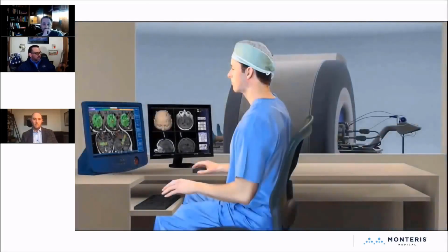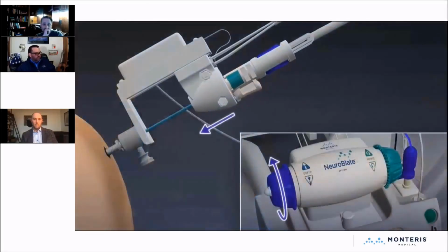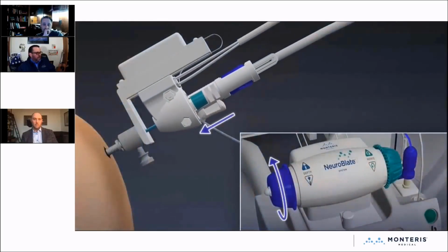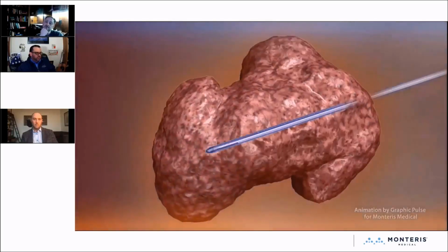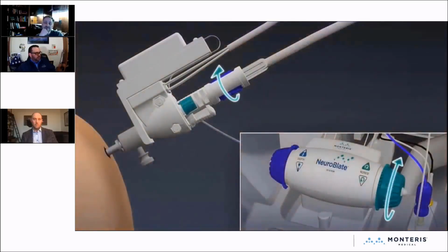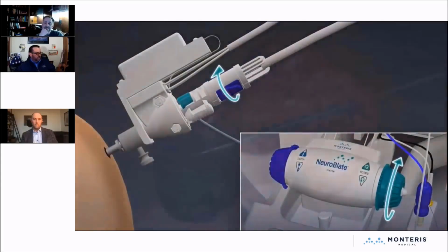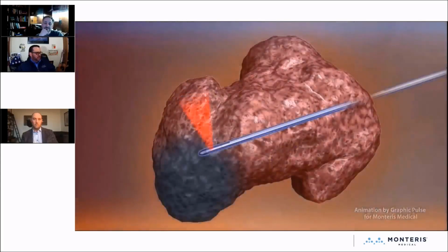From there, we go ahead and get a volumetric scan to show where the probe actually landed. We use the robotic apparatus to drive the linear position of the laser probe, as well as changing the rotary direction of our side fire laser probe. And here you can see an animation of what that looks like at the back side of the scanner as it's turning within the target volume.